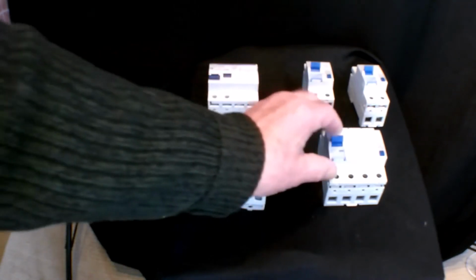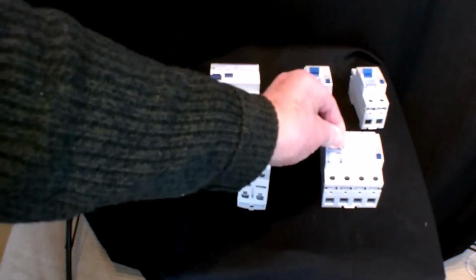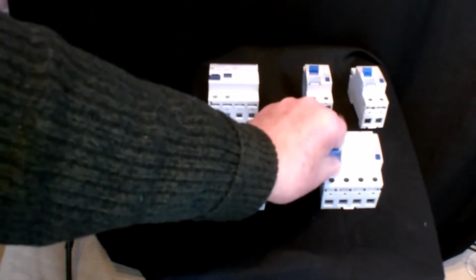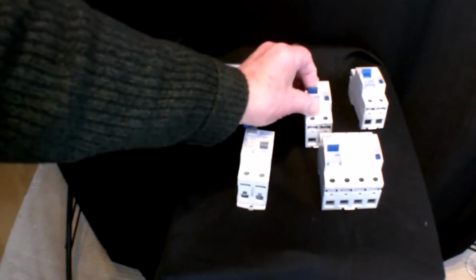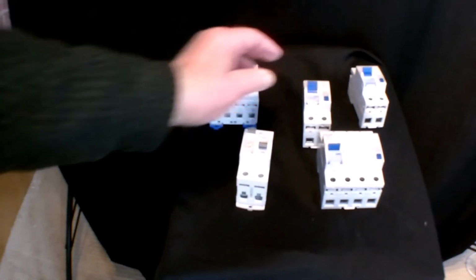Some of the newer RCDs have a position in the middle that they trip to if they trip. So you may have to move it down, as in this one, and then push it up to reset it. It's just to give you the indication that it has automatically tripped rather than being switched off.